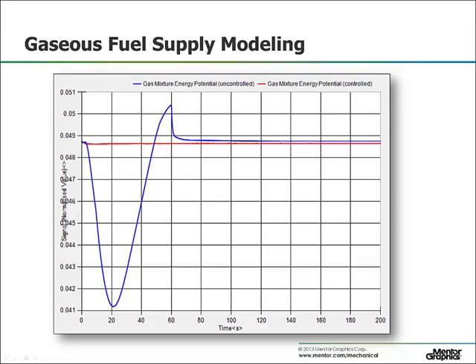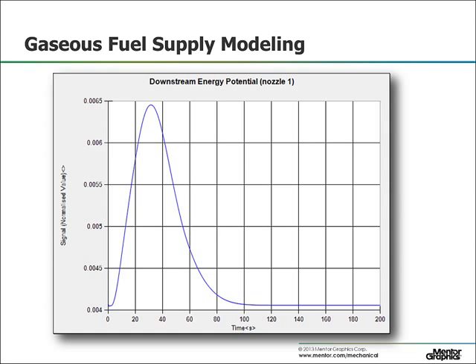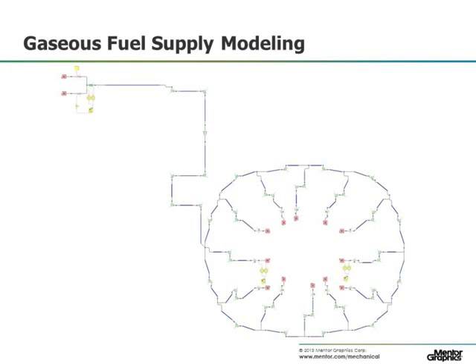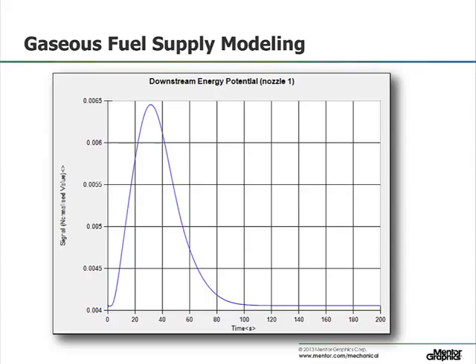Again, here are the results just after the mixing point of the uncontrolled heating value result and the PID controlled heating value result. Although the controlled value mixing results look good at the mixing point, if we look downstream at the first inlet nozzle, and let me back up and show you, this is the first inlet nozzle, you can see that there's still a variance. In this case, it's even worse, up to 40%.